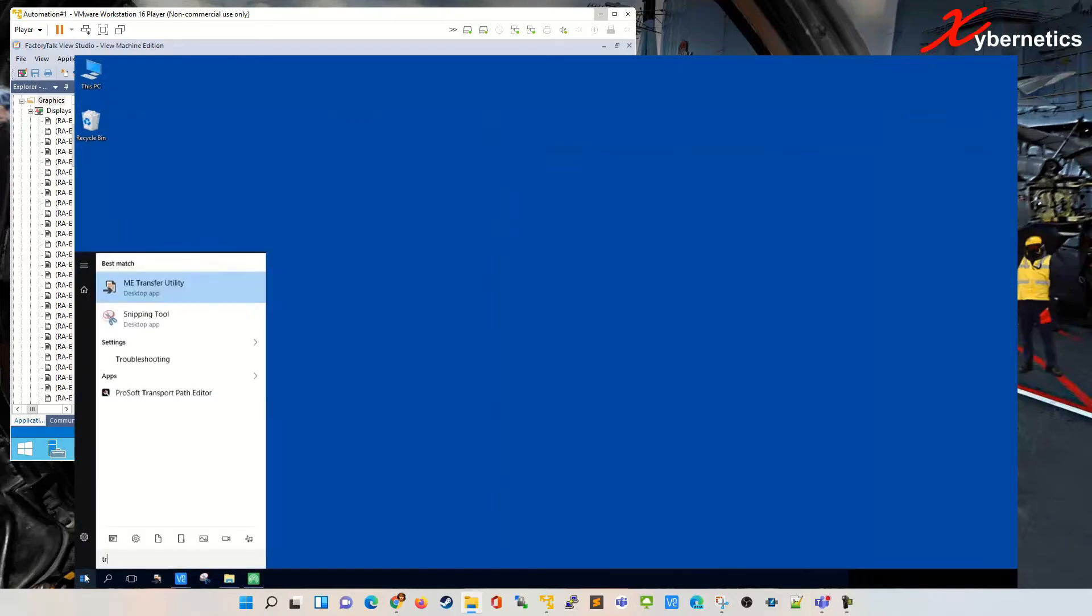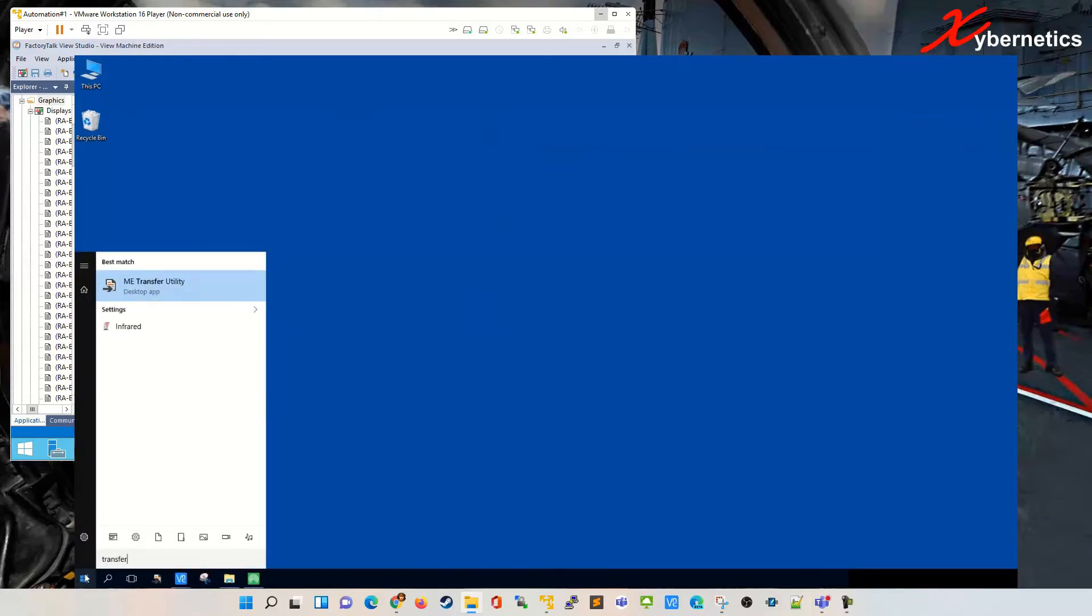Okay, I've moved my .mer file into this computer which is on the same subnet as the panel view. To download or upload the MER file from the panel view you need a tool from Rockwell called Transfer Utility. You click on the start window here and you type the word transfer. It comes up with ME Transfer Utility.